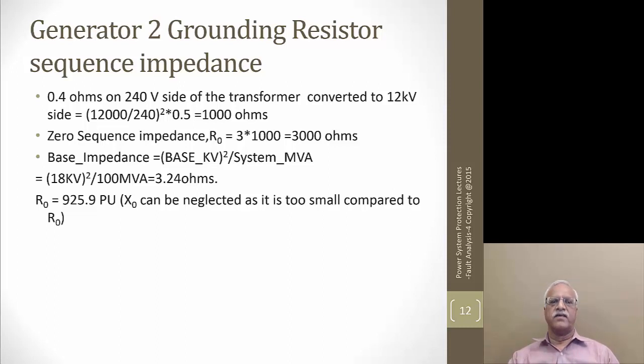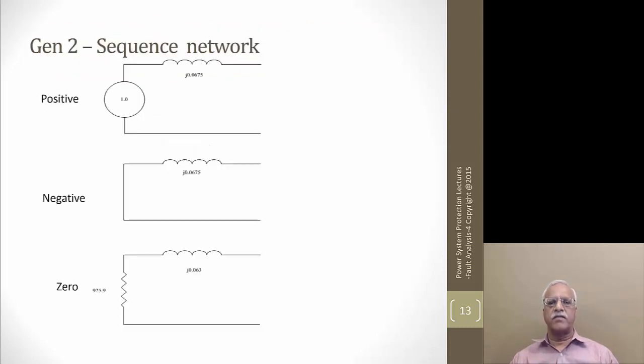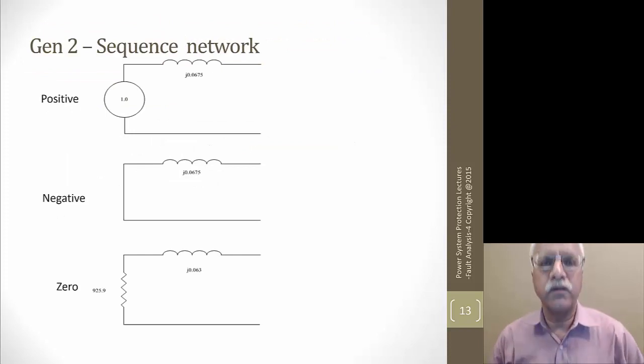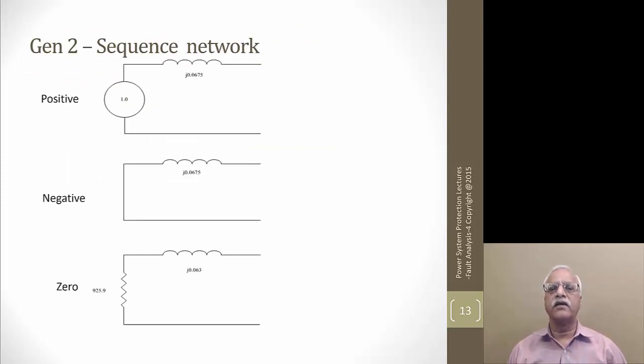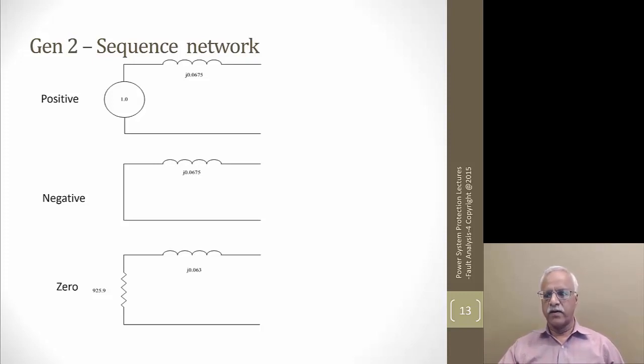Generator two is grounded through 0.4 ohms on the 240 V side of a transformer with a primary at 12 kV. Going through the same process, it turns out to be 1000 ohms on the 12 kV side, and because it is connected at the neutral it gets multiplied by 3, becoming 3000 ohms. Converting to 18 kV base, R0 turns out to be 925.9 per unit — almost infinite compared to the rest of the impedances. The zero sequence network for generator two is almost purely resistive.